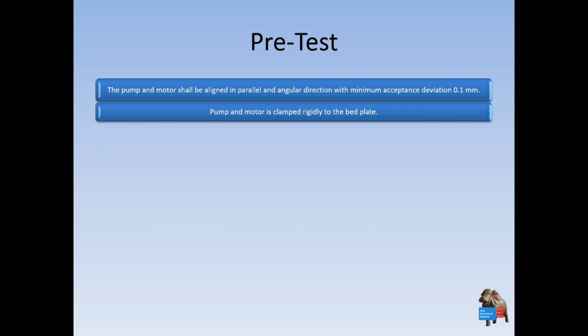And then the pump and its frame after assembly should be rigid to the floor, because of the energy and centrifugal force from the motor. You don't want the pump or the frame suddenly moving to the right or the top. So you have to ensure that the pump is stuck very well to the base frame and the frame very well to the floor.